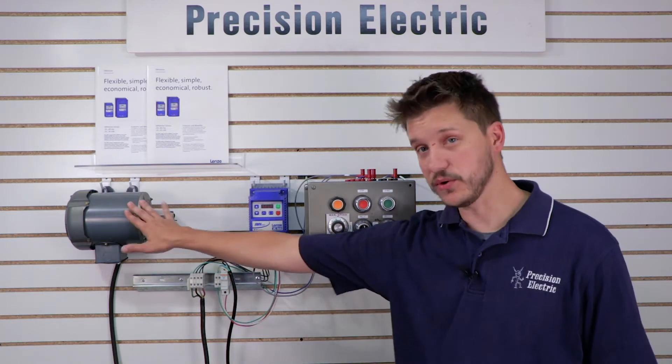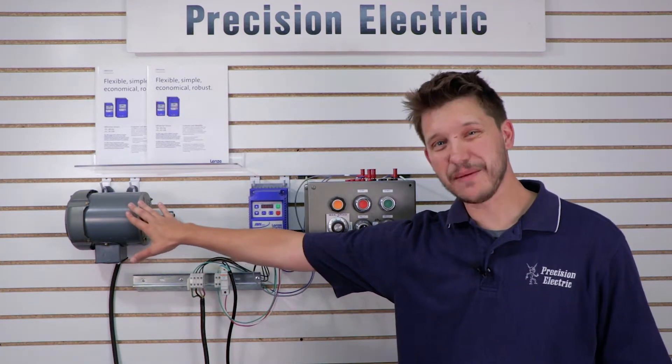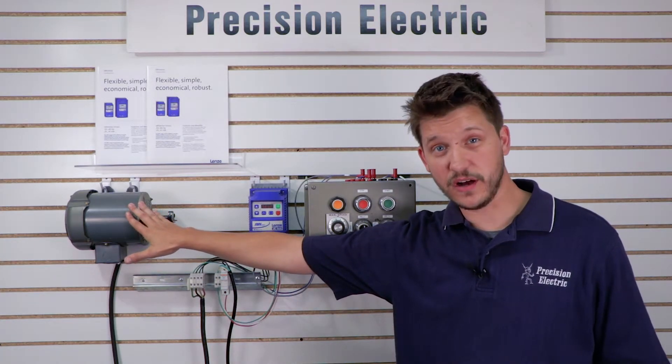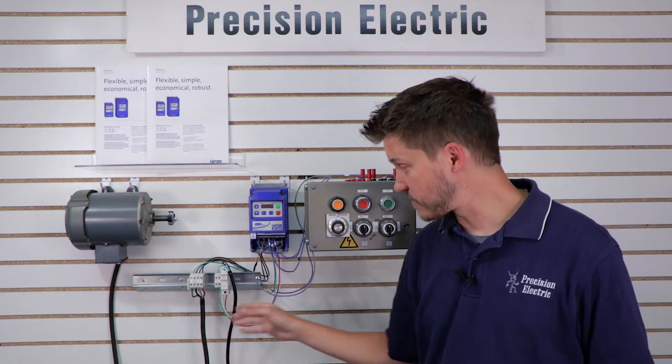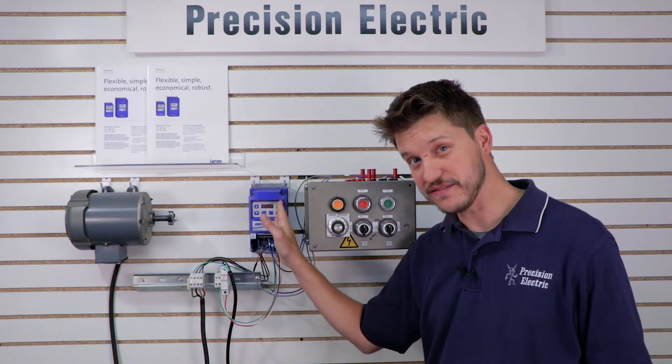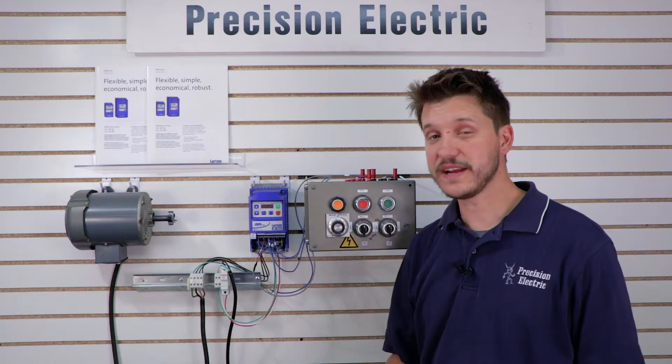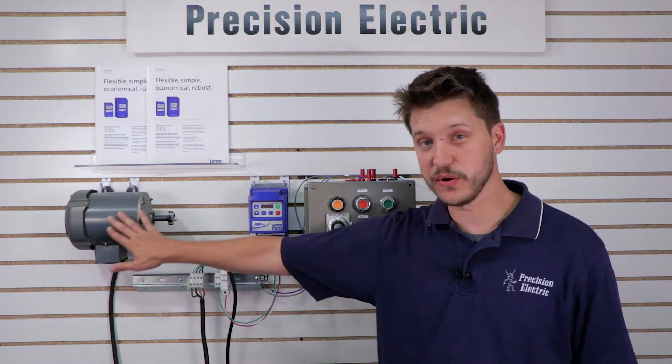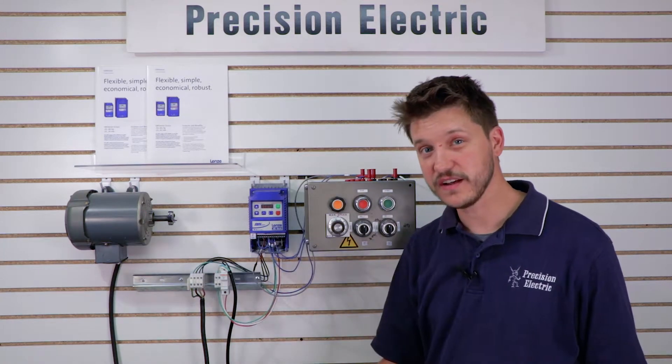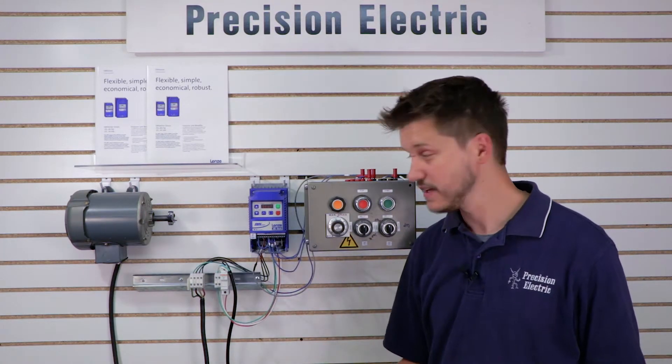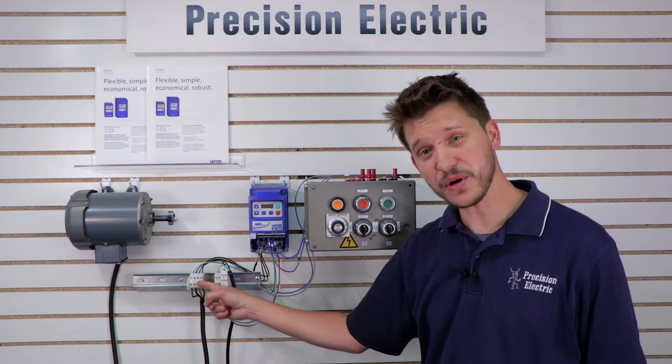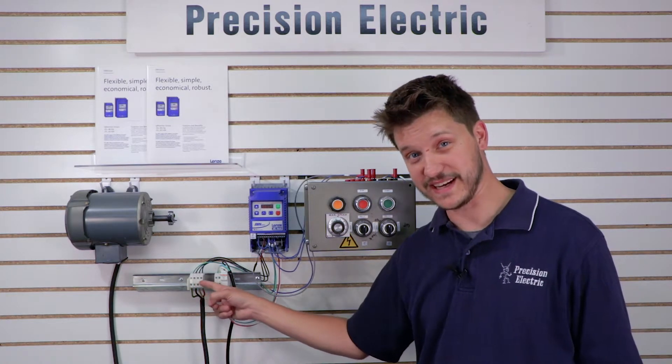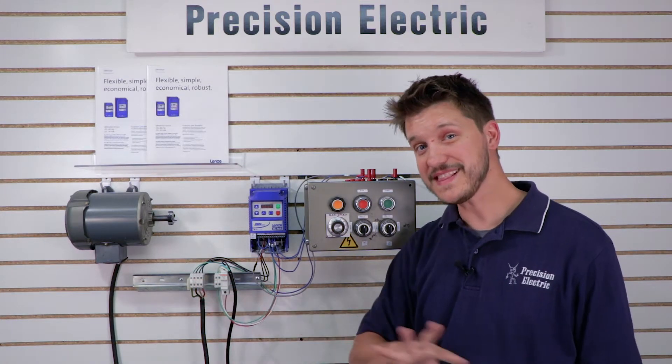The second part is actually protecting your motor. A real common issue that we run into when people call with these drives is they wire something between the output of the drive and the motor itself. There can't be anything wired between the output of the drive terminals U, V, and W and the motor itself. You can't wire it through a starter, you can't wire it through a contact block. You can wire it through terminal blocks, that's fine because you're maintaining a constant connection, but nothing that can open.